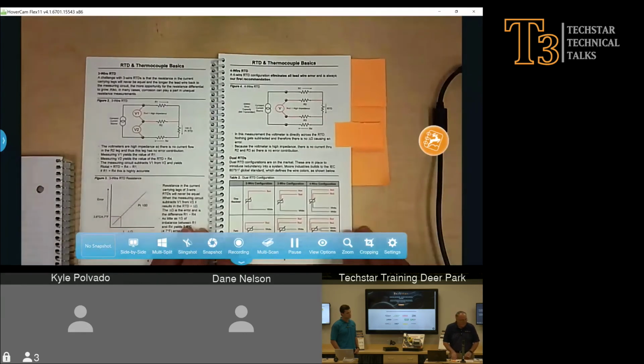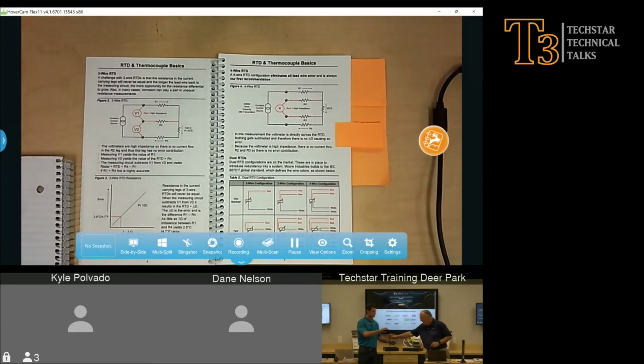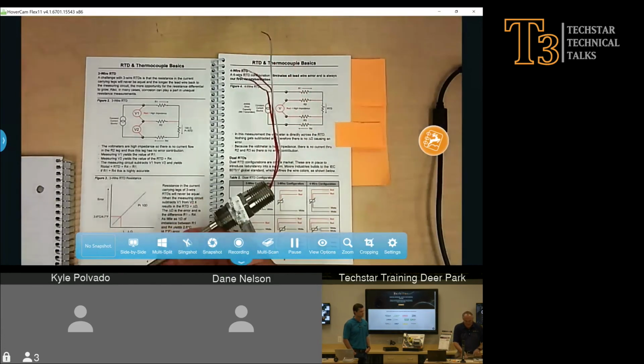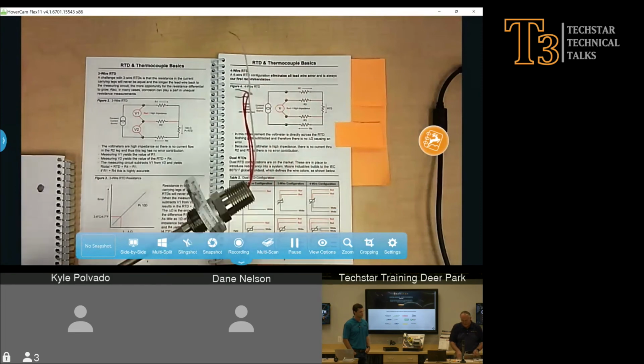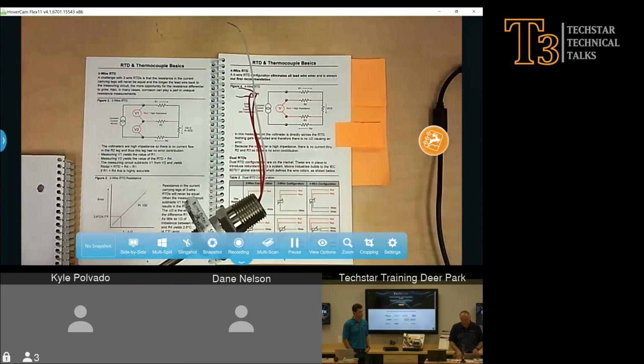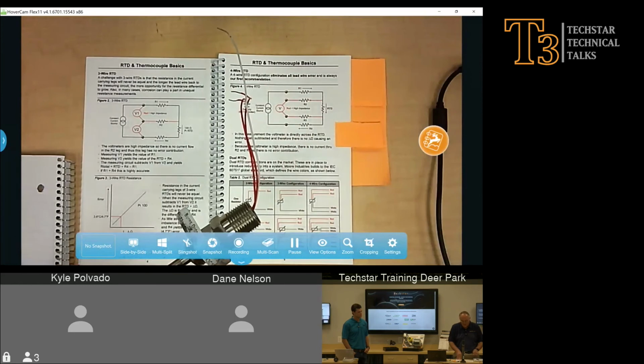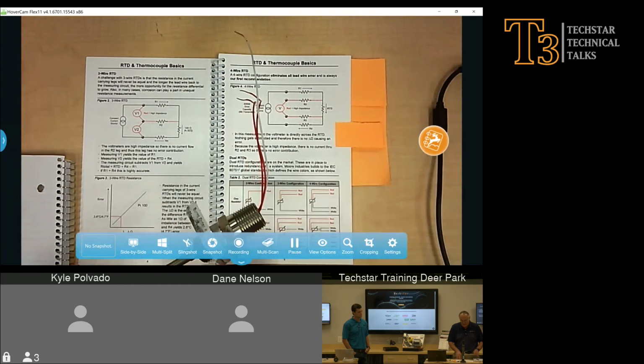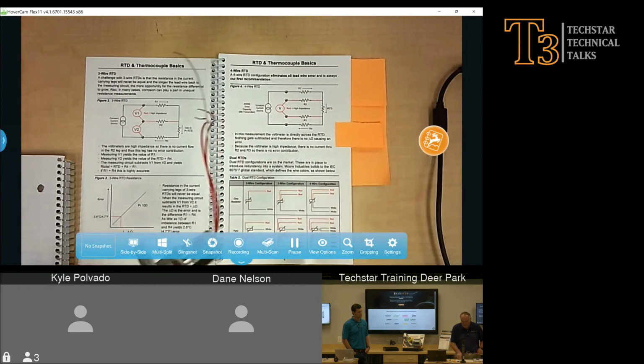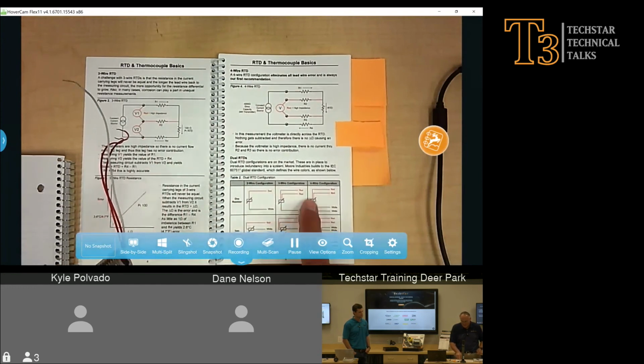And I flagged just a couple of things on this. So this one is here. Where is the 3-wire? Have you got that one? Yeah. So this is probably the number one RTD that we see. It's a 100-ohm platinum 3-wire. And hopefully we told you why you want to use a 4-wire, because it is self-compensating. So you don't have to worry about wire length or corrosion. This has a 385 alpha. And right over here is how it's wired up.